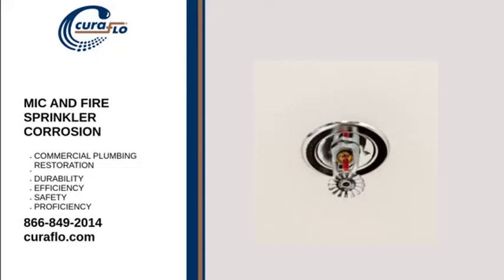Currently, a common solution to alleviate the problem is to drain completely and charge with nitrogen gas or truly dried air. A more recent solution is to coat the interior of the sprinkler pipes with epoxy, acting as a barrier coat between the harmful microbes and the sprinkler pipes. Fire sprinkler systems failing prematurely.